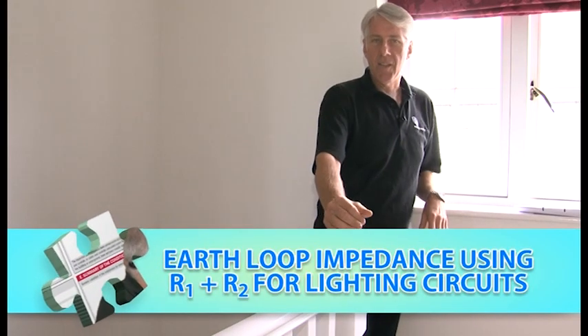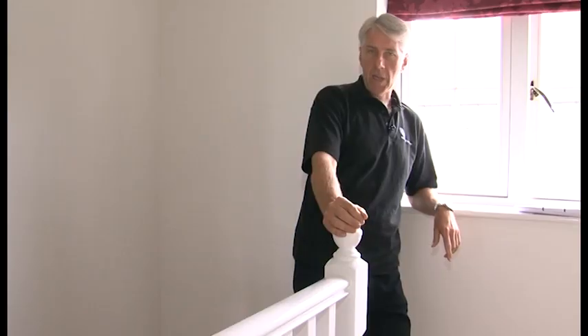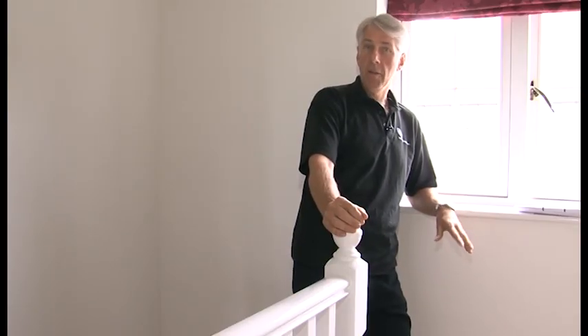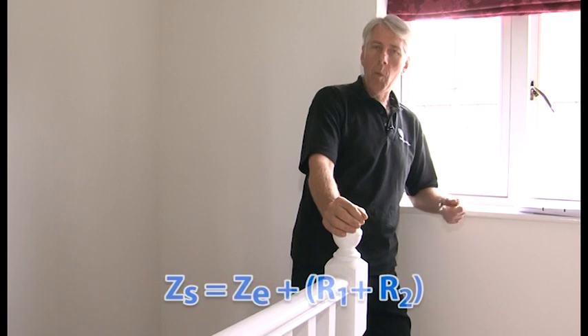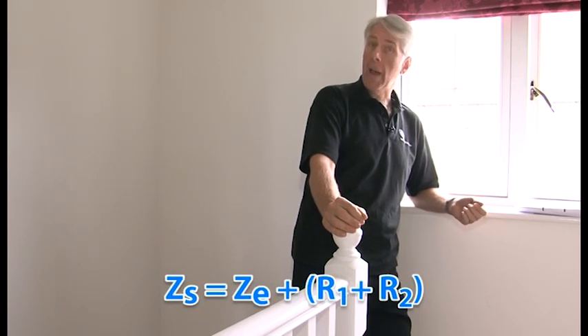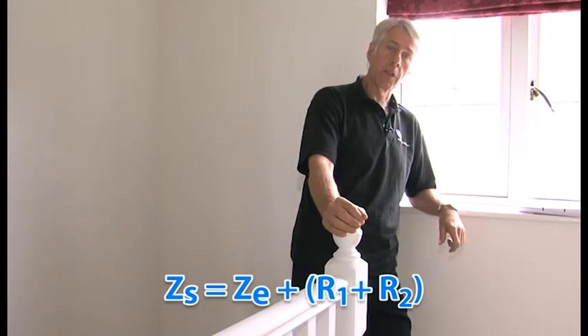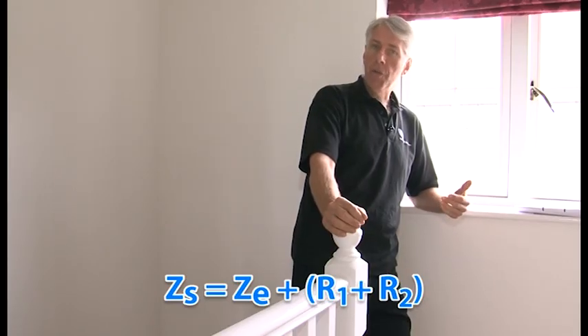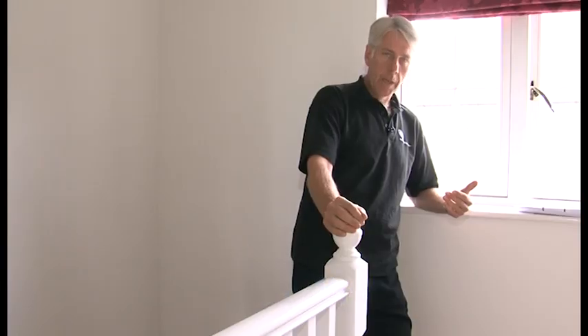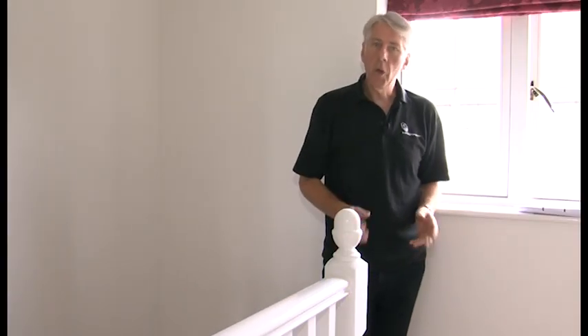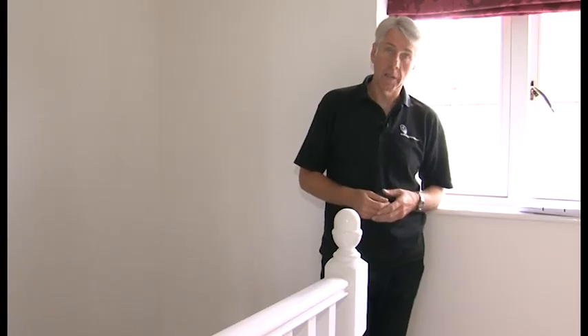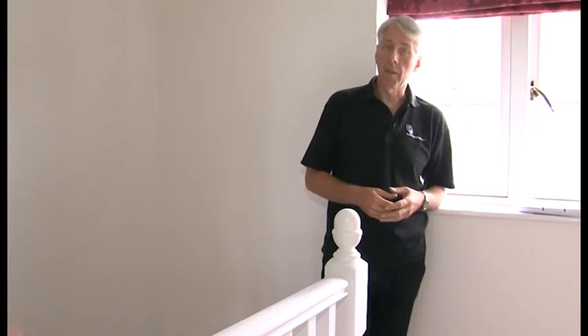The next dead test Tony will undertake will be an R1 plus R2 test at the furthest point of any radial circuit, for example, the lighting circuits. R1 plus R2 will give us a value which, if added to the earth fault loop impedance external to the installation, ZE, will give us our earth fault loop impedance for these circuits. Now doing this test means that Tony will not have to work on live exposed electrical conductors, so reducing the chance of receiving an electric shock. This then complies with the Electricity at Work Regulations 1989, which only allows work on or near live conductors if there is no other way of obtaining the results.